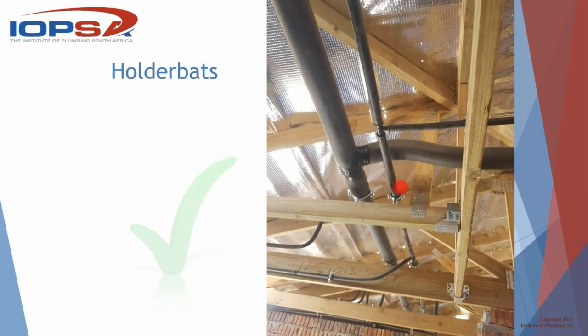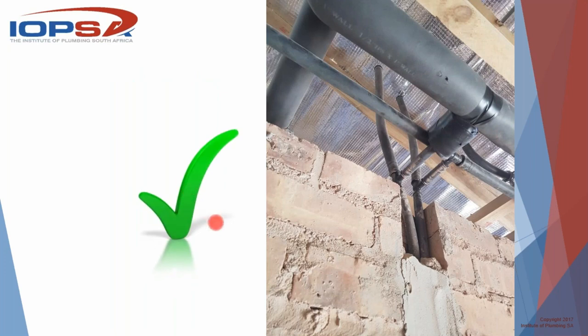It's a new home. This is his hot water reticulation, all lagged in R1, not an exposed piece of pipe to be seen. Brackets around the lagging, everything's lagged right up to the point where it disappears into the wall, or a couple of hundred mil before. And really, there is nothing more you can actually ask from an installer. You'll notice as well that even the cold water pipes have got the same type of insulated brackets.